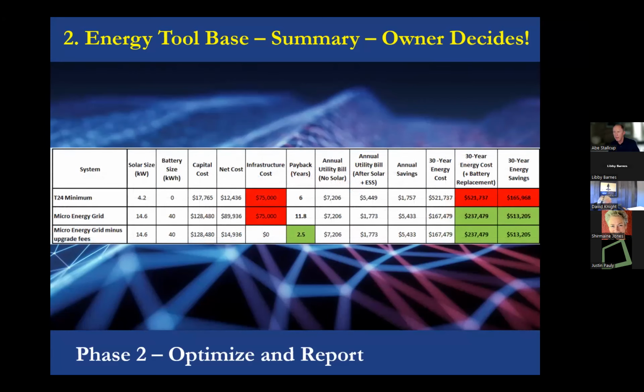Before I move on, I want to talk about the ability to keep a service, this 400 or 600 amp excessive service, down to 200 amps. We're actively working with local building departments in several jurisdictions and have come up with a solution. We work with various electrical engineers on a hybrid solution between off-grid and grid connected, where we can use only 200 amps of service as the minimum, but still provide a 600 amp service to the house by using multiple sources of input. This is the microgrid concept, keeping the service at 200.